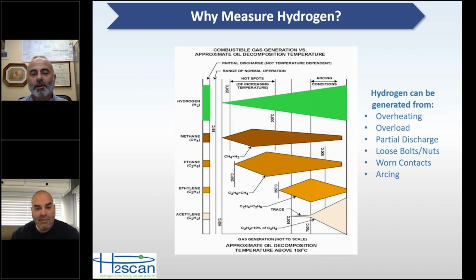Usually that hydrogen will stick around at least a few weeks to a few months. And like I said, if you have a really good tight transformer, it will actually stay in the transformer for years. So it is a key gas to look at. And the great thing about hydrogen is there are a lot of low-cost sensors on the market. Like I said, hydrogen will tell you if there's something serious going on in your transformer.